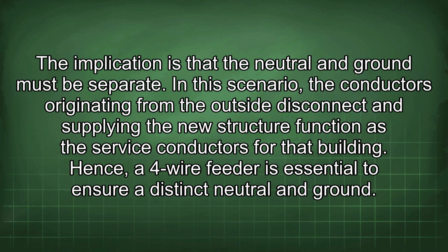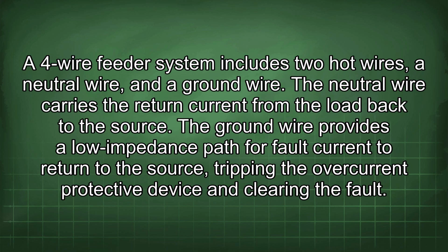In this scenario, the conductors originating from the outside disconnect and supplying the new structure function as the service conductors for that building. Hence, a 4-wire feeder is essential to ensure distinct neutral and ground. A 4-wire feeder system includes 2 hot wires, a neutral wire, and a ground wire. The neutral wire carries the return current from the load back to the source. The ground wire provides a low impedance path for fault current to return to the source, tripping the overcurrent protective device and clearing the fault.